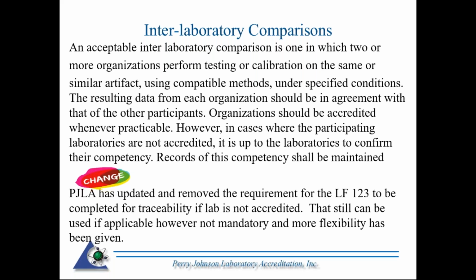However, for smaller organizations, most of the time when I see an interlab comparison it's us and another lab - bare bones minimum, the more the merrier. If the other lab is not accredited, then you're going to have to put the proof in the pudding. If they are a calibration lab, the LF-123 is another way to show competency if they're not accredited. If they are accredited, then that scope of accreditation would fulfill the competency requirement.